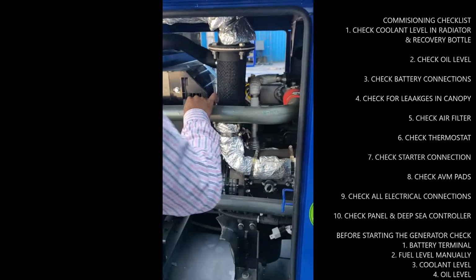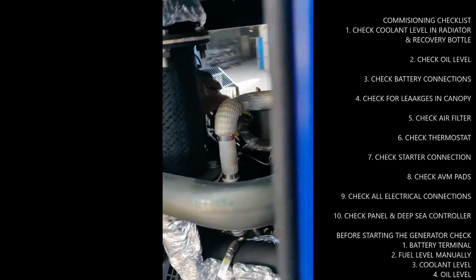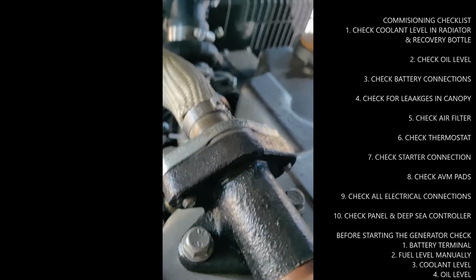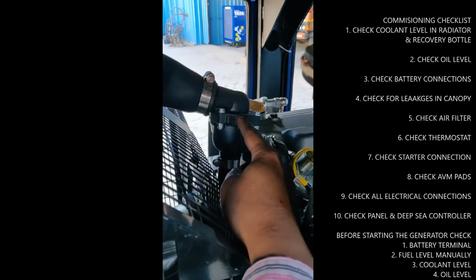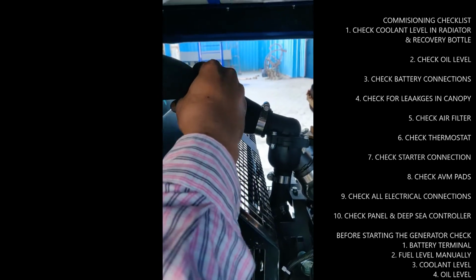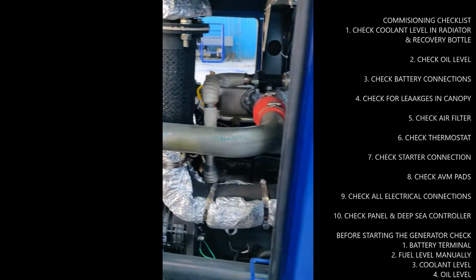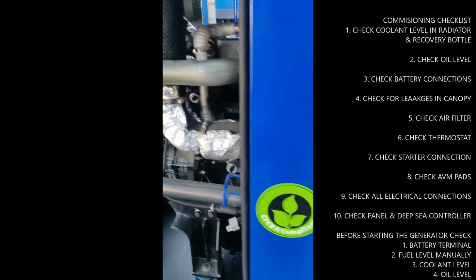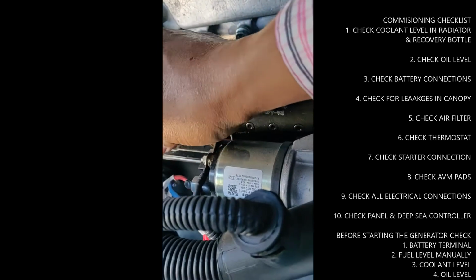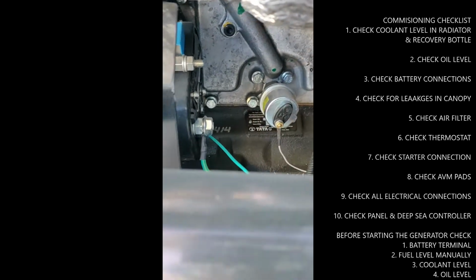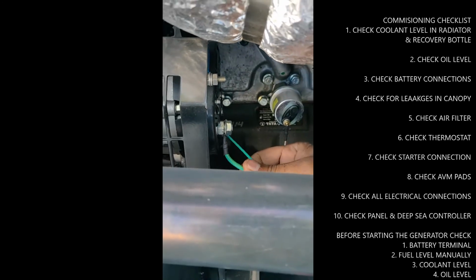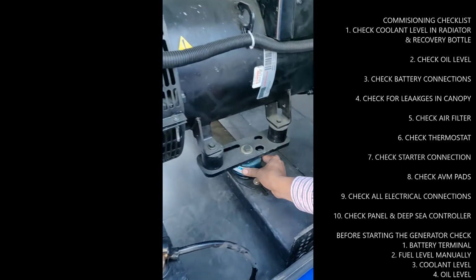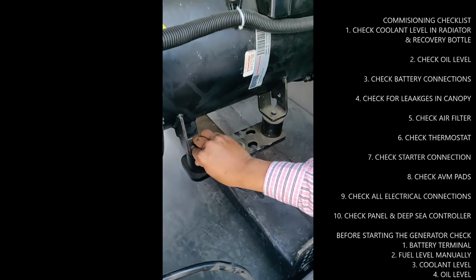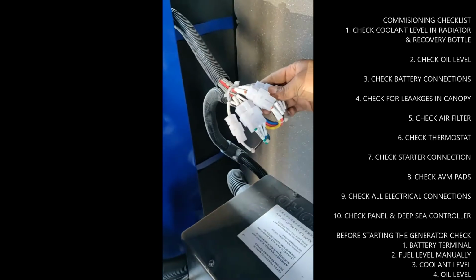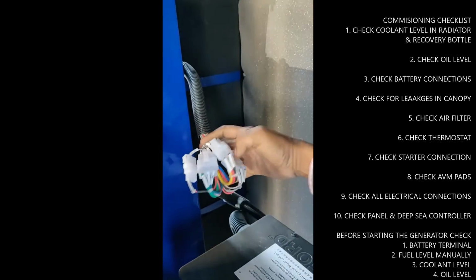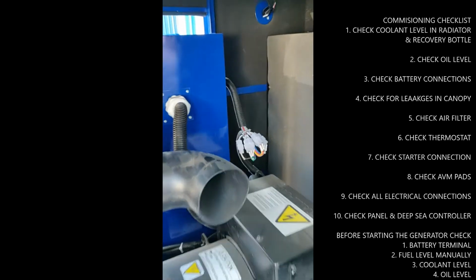Check the thermostat, which is placed just behind the head of the engine. Check that the thermostat is fitted well and is not loose. Here you can see that it is perfectly tight. Check the hose and the clamps. Clamps should not be loose at any time. Now coming to the starter connection, it is important to see that it is properly tight. All electric connections related to the oil sensor and the charging alternator are tight and okay. Check the AVM pads. AVM pads are properly tight and the fitting is not loose at the base of the alternator. All electrical connections with the harness that come from the alternator are attached in the panel here. Check that all the fittings are proper and properly connected to each other.